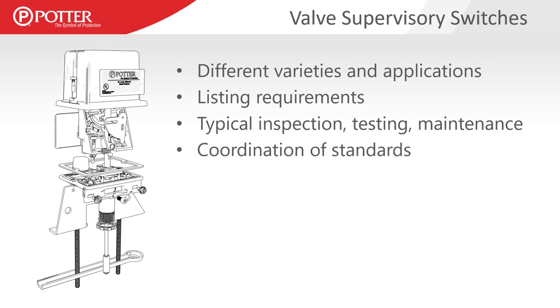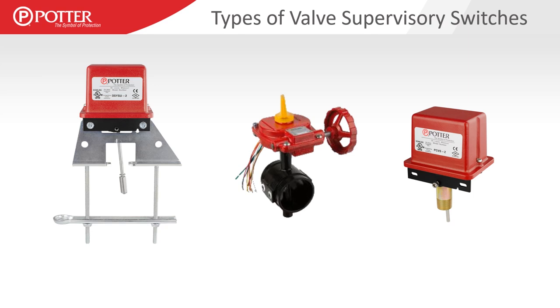There is a bit of coordination of standards that takes place with valve supervisory switches as well. The types of valve supervisory switches vary — depending on the type of valve, whether it's an OSY (outside screw and yoke) valve, a butterfly type valve, or specialty plug type switches used in circumstances where there's no other way to supervise a control valve. Any valve on a sprinkler system is suitable for supervision — there's no excuse for not supervising the control valve on any sprinkler system.